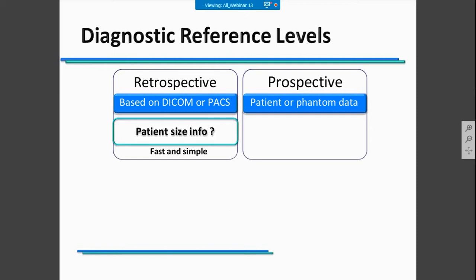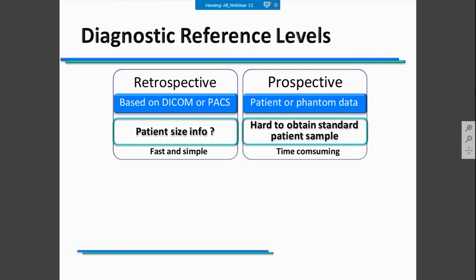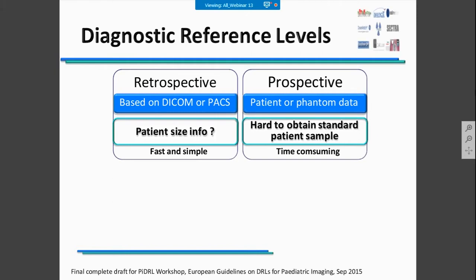To calculate DRLs in the prospective mode, you must be aware that it is hard to obtain standard patient samples, and if you do it using a phantom, the obtained value is not so realistic. So this method is more time-consuming. Don't forget that at the moment there are many dose monitoring systems that can calculate DRLs for you. However, it's important to understand how they are calculated and how to manipulate the data you obtain with these systems.